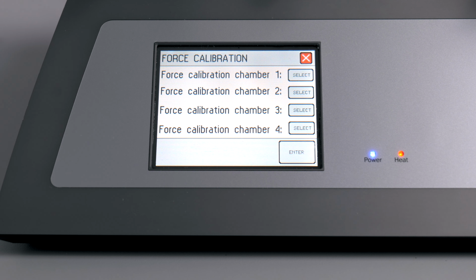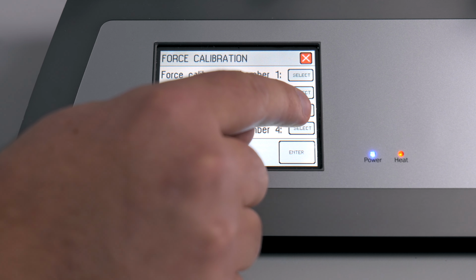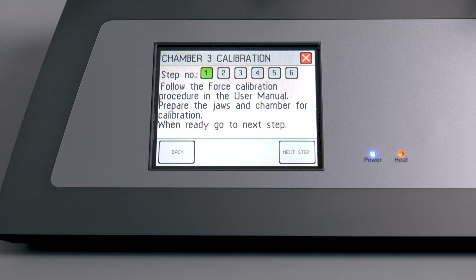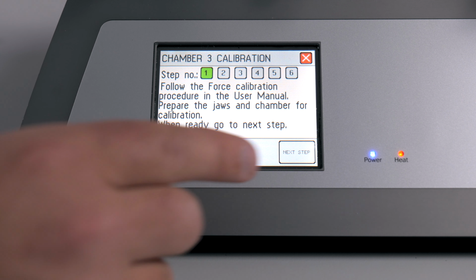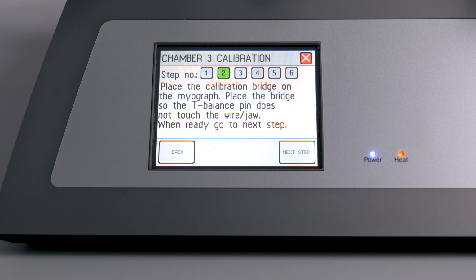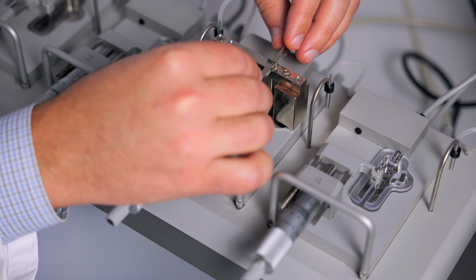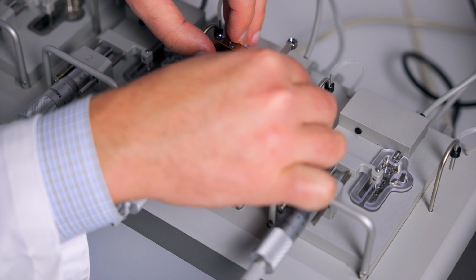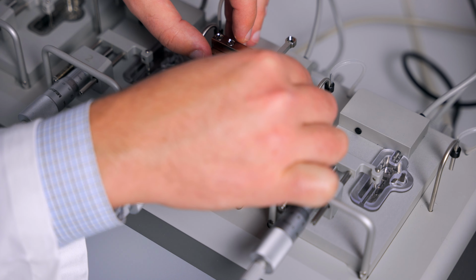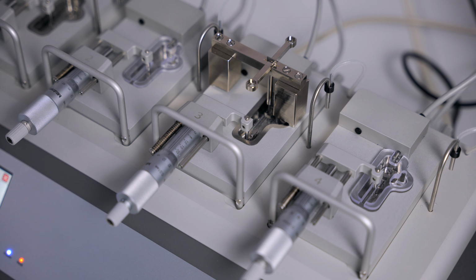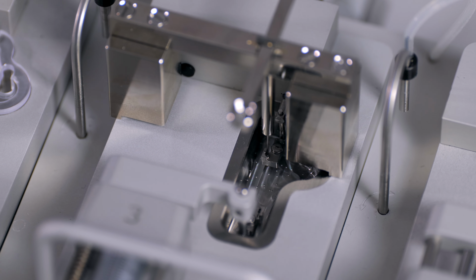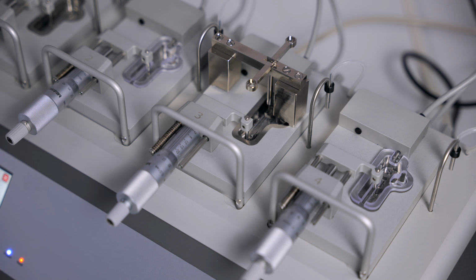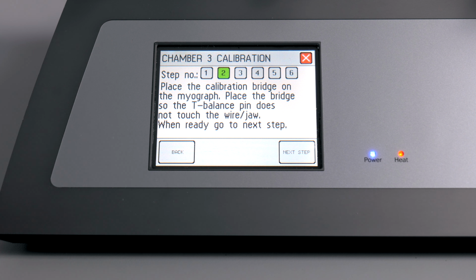To show the calibration for the clamp mounts, we will be going to chamber 3. So we will highlight chamber 3 and select Enter. Now this is the same process, the only difference will be where we place the calibration bridge and T-balance. So we can go to Next Step. Step 2 asks us to place the calibration bridge and T-balance. For the clamp mounts, the final position of the T-balance should be dropped behind the clamp on the left side. Again, it should not be touching the mount before you proceed with the calibration. Once you have the calibration bridge and T-balance in place, select Next Step.